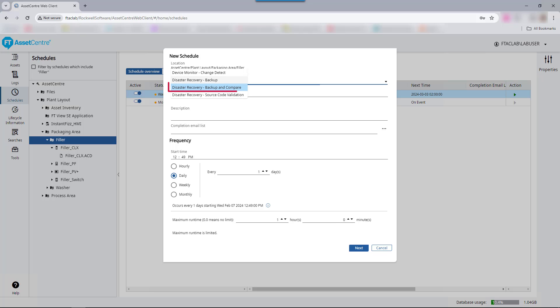Backup and Compare will upload the asset's configuration file and compare it to a designated version already checked into the archive, but by default will not check the uploaded file into the archive. To use this function to also check the file into the Factory Talk Asset Center archive, the Promote New Upload to Master property of the device within the schedule must be set to true. This will cause the uploaded file to be checked into the Factory Talk Asset Center archive when differences are found between it and the latest version already checked in and will automatically promote the uploaded version as the master of the file.